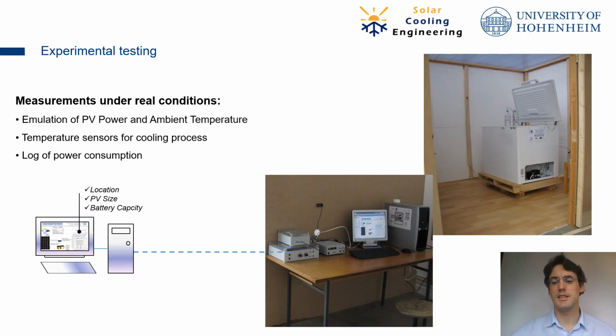It is important that this happens at the same time, because during the day you have a lot of energy available, so the batteries have a high SOC, state of charge, but at the same time you have a high ambient temperature, so the efficiency of your refrigerator is lower, the COP, the coefficient of performance, and the thermal losses are also higher. So this compensates somehow, and it's important to measure both at the same time, that you emulate your PV power and your ambient temperature simultaneously.